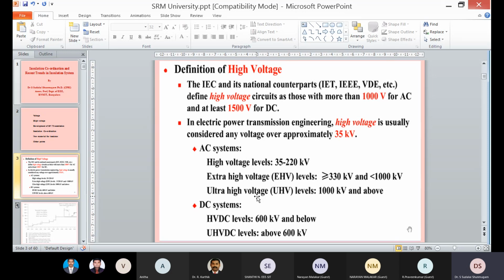Why does power transmission have different nomenclature? Up to 220 kV, the nature of the faults occurring in the system is quite different when compared to the EHV level. It means the fault occurrence and the impact of faults at HV won't be the same as at EHV level, and the fault impacts won't be the same as at UHV level. Each level has its own peculiar characteristics with respect to system faults. That is why we have this classification: 35 to 220, 330 to 1000 kV, and 1000 kV and above. And India has systems on all three levels right now in the world.